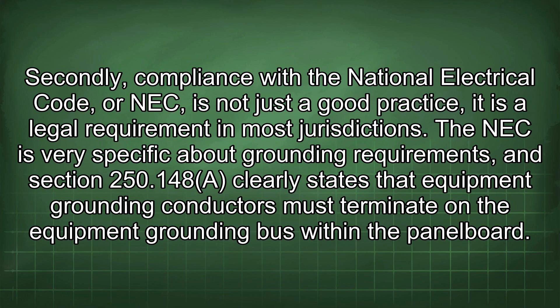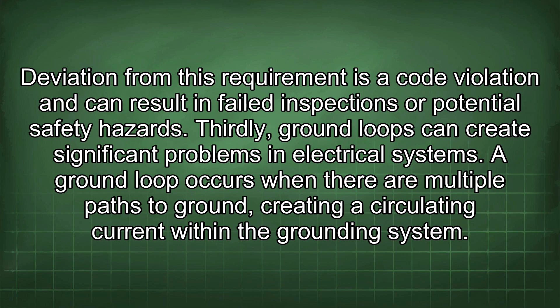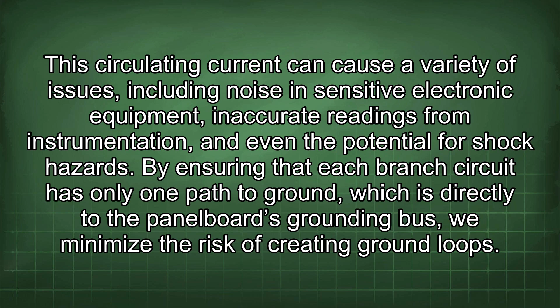Thirdly, ground loops can create significant problems in electrical systems. A ground loop occurs when there are multiple paths to ground, creating a circulating current within the grounding system. This circulating current can cause a variety of issues, including noise in sensitive electronic equipment, inaccurate readings from instrumentation, and even the potential for shock hazards. By ensuring that each branch circuit has only one path to ground, which is directly to the panel board's grounding bus, we minimize the risk of creating ground loops.